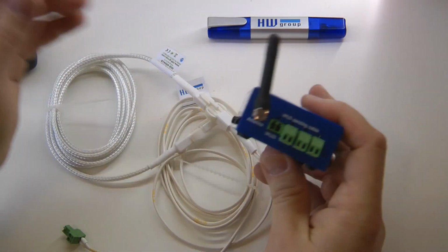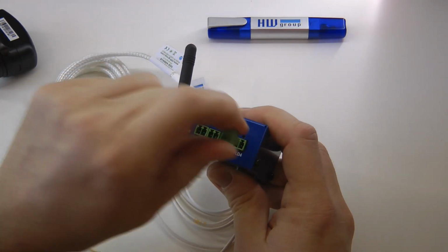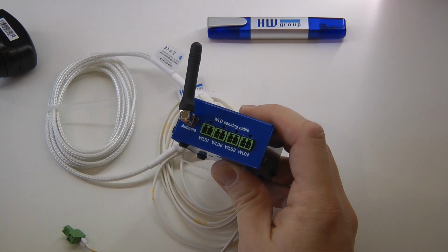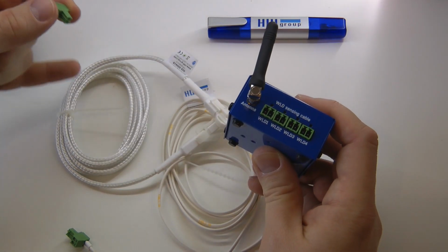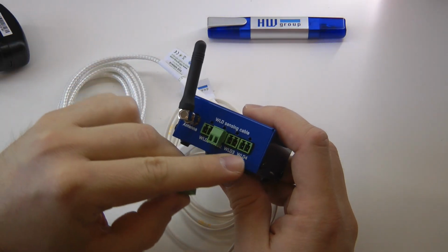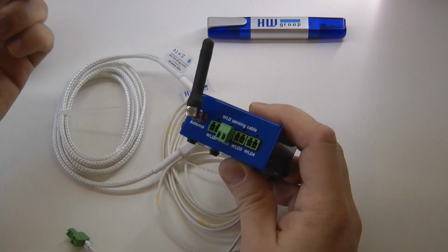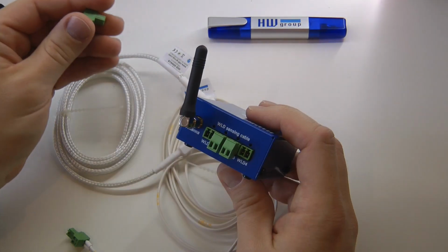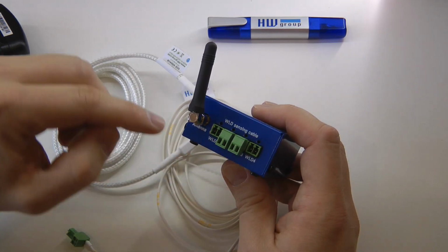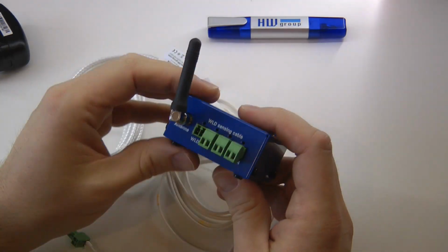And on the other side, we have 4 connection points. So this single device can detect 4 different water detection loops. And as I said, each loop can have multiple of these 2-meter detectors. But if you're using these detectors on multiple inputs, you would actually be able to tell which line is detecting flooding. So it could be more convenient to use multiple inputs rather than just one input and a really long cable. And we also have a Wi-Fi antenna.